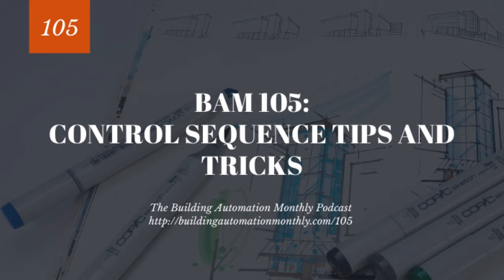And so that's the time when, before it ever gets to that point, you can go and actually rearrange stuff, submit it as an RFI, and say, hey, I really recommend that we open the isolation valves before we turn on the chiller, especially with this type of chiller, which has an internal flow sensor, or does not have an internal flow sensor. So as soon as I enable the chiller, it's going to try to turn itself on. I really recommend that we have the isolation valves open first per the sequence, especially since this is being commissioned. And then you submit that up the chain in a construction project, which is making me realize I really need to have another episode about construction projects, because that seems to be a lot of the questions I get: the construction process.